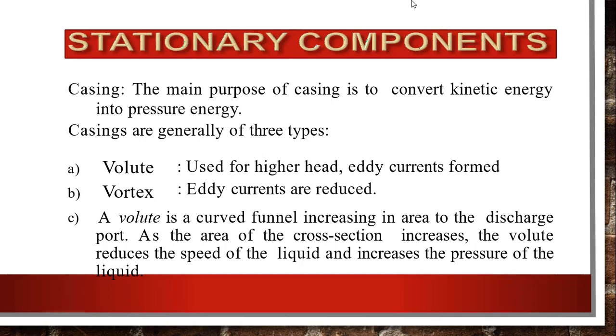The main purpose of the casing is to convert kinetic energy into pressure energy. Casings are of three types. The first is volute, used for higher head where eddy currents are formed. The second is vortex, where eddy currents are reduced. The third also involves a volute — a curved funnel increasing in area toward the discharge port. As cross-sectional area increases, the volute reduces liquid speed and increases liquid pressure.